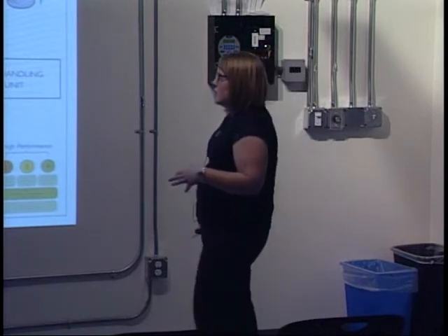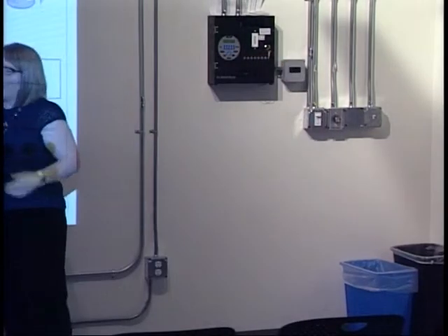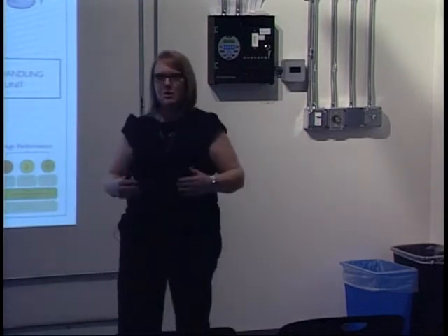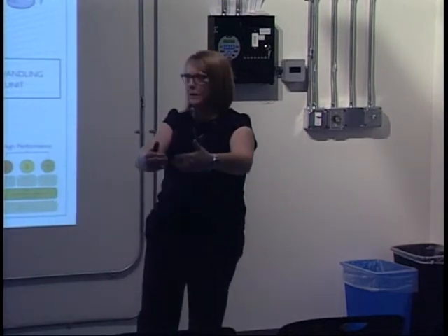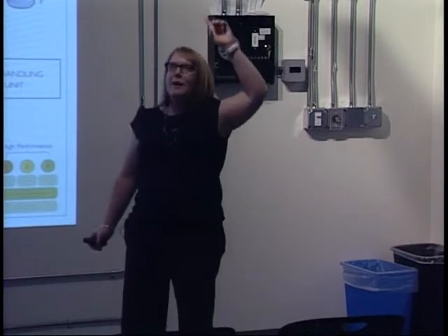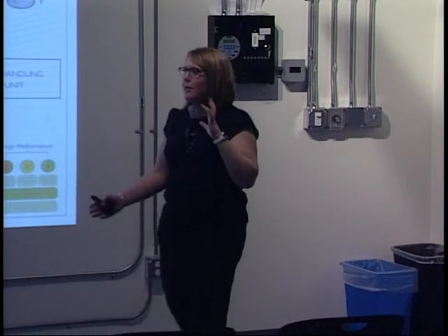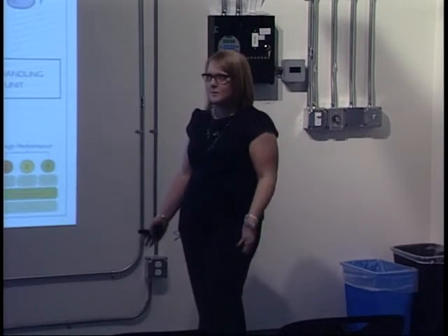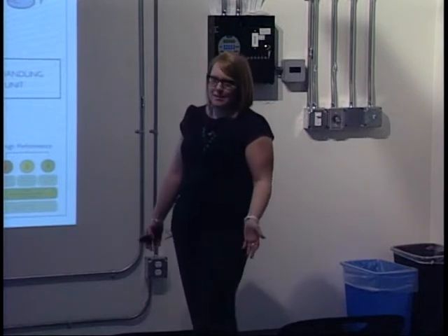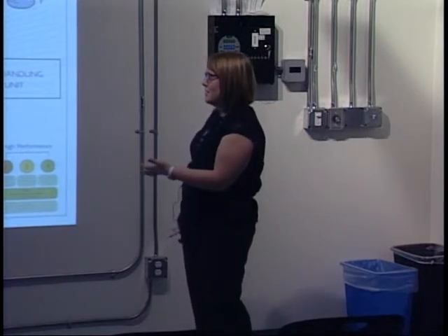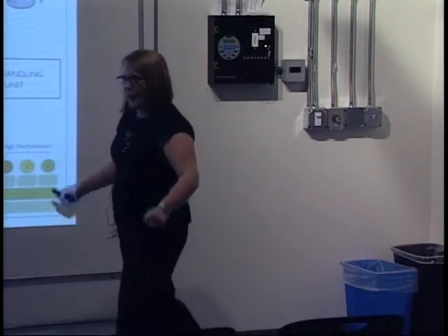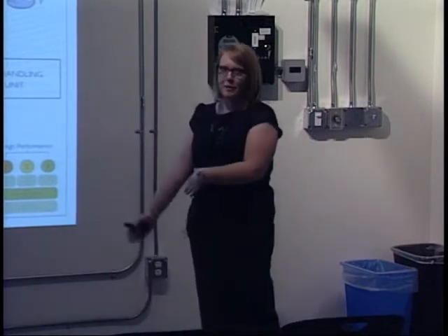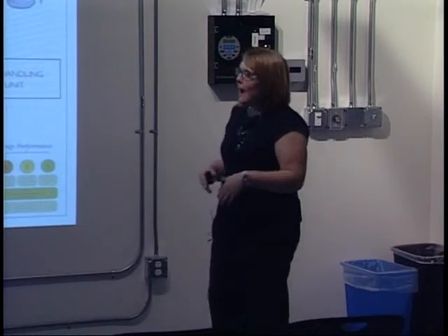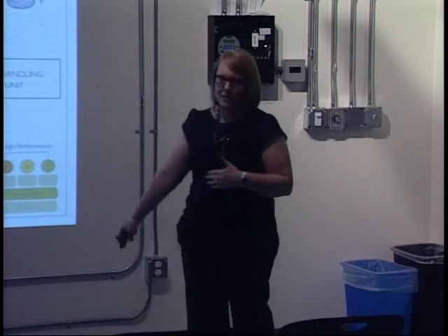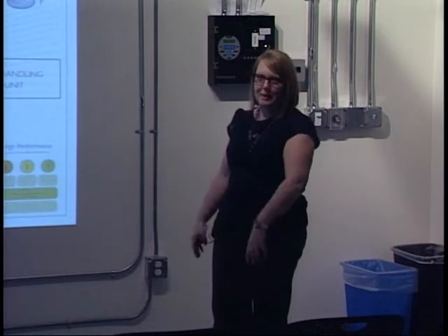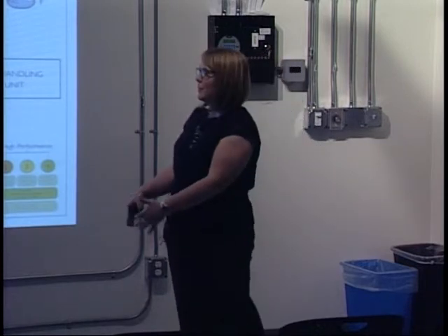The way that they suggest doing that is putting the supply air grill at the base of the patient bed, so on the wall adjacent across from the patient foot, and putting the return or the exhaust above the patient head. That's the way that the ventilation effectiveness is the highest in that case, and operationally, it makes the most sense. One of the things you want to be careful with that kind of system is that some wheelchair or bed or whatever doesn't get placed in front of that supply air grill and block it. The foot of the patient bed is a very highly trafficked area. It's not a place where medical equipment gets left as often. So it's a good place to put that supply air grill.